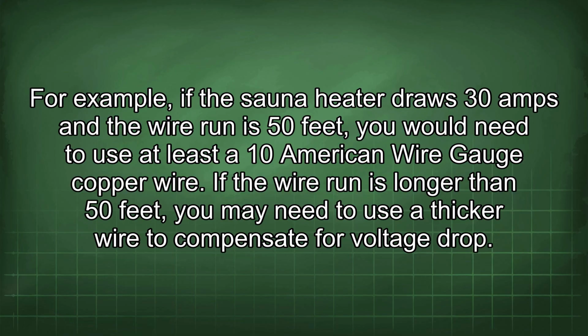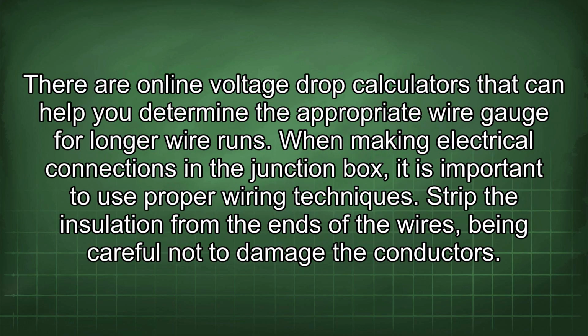If the wire run is longer than 50 feet, you may need to use a thicker wire to compensate for voltage drop. There are online voltage drop calculators that can help you determine the appropriate wire gauge for longer wire runs. When making electrical connections in the junction box, it is important to use proper wiring techniques.